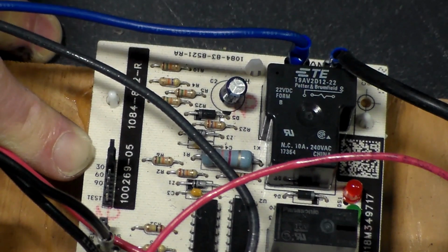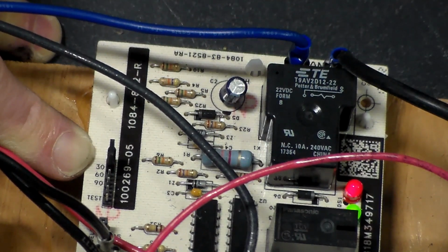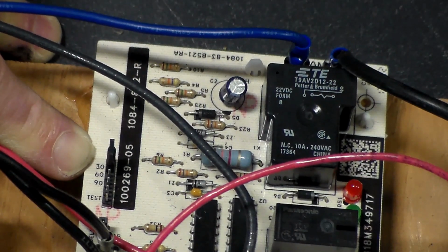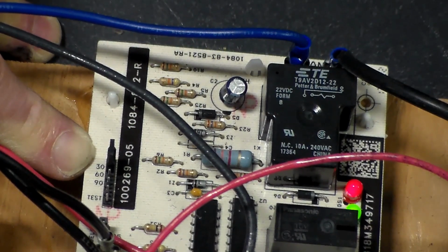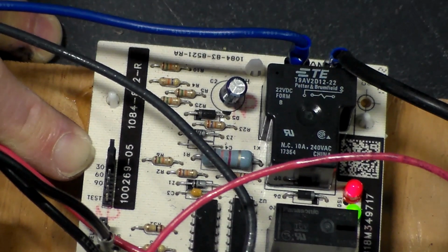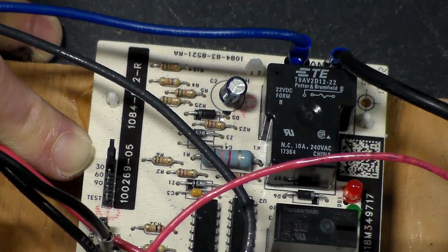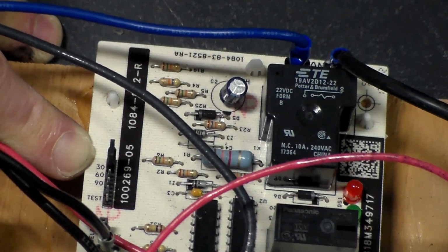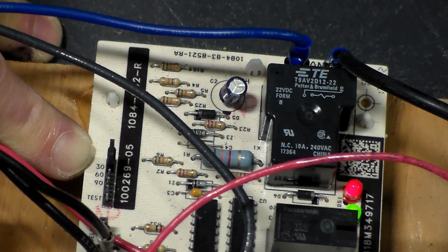So basically, this board right now is set for 30. It's going to try to defrost every 30 minutes of run time. So let's say it runs for 10 minutes, then 10 minutes, and then 10 minutes again later. When it hits that 30-minute run time mark, not real time, run time, then it's going to try to defrost. And if the sensor says, yes, I'm frozen, it'll go ahead and defrost until the sensor says it's thawed out, or until that 10 minutes goes by that's programmed into the board. We can't adjust that. So to start with, my board is set for 30. It's going to try to defrost every 30 minutes. If the sensor is showing closed, it'll defrost until the sensor shows open, or until that 10-minute timer that's built into the board itself goes by.